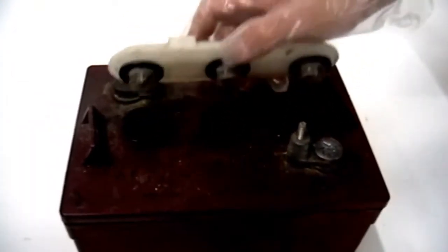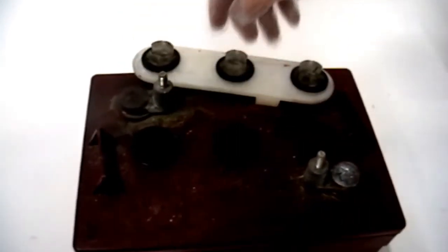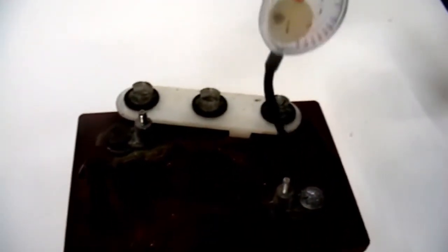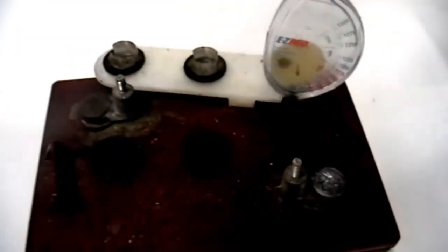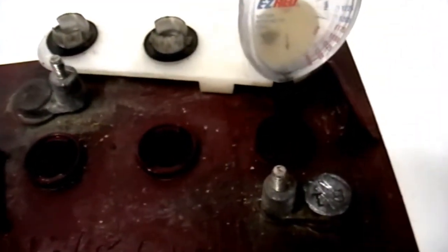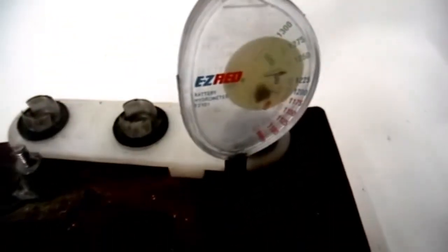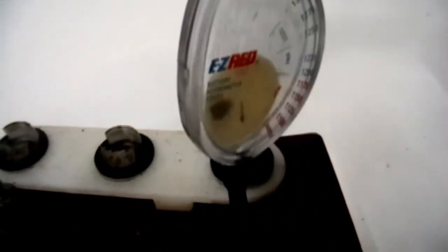To use a hydrometer, carefully remove the battery caps. Insert the tube of the hydrometer into a battery cell. Compress the pump to fill the chamber with solution. It is best to do this at least twice for each cell to make sure you get an accurate reading.